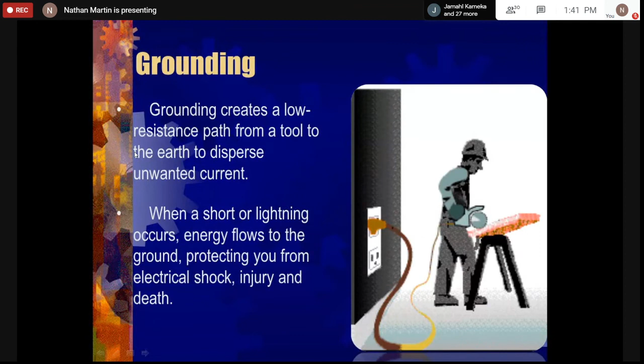When I'm teaching electrical installation, I always tell students it's even more important than anything else in the installation. Without your ground, that is one of the main things the government inspector will check, to ensure that your ground resistance is okay. Because without your ground, your earth, your breakers will not trip. You will have a circulating current, the wires will overheat, and then they will catch fire, start to burn, and you will have an electrical fire - which will lead to a bigger fire and the house burning down.